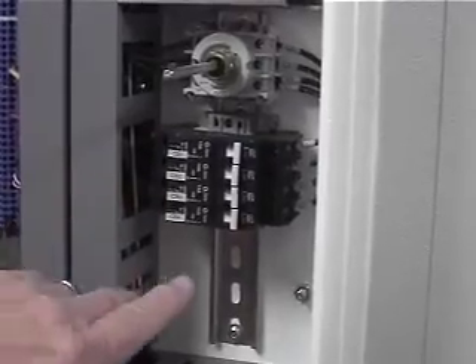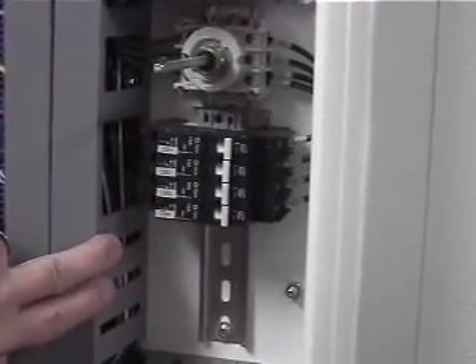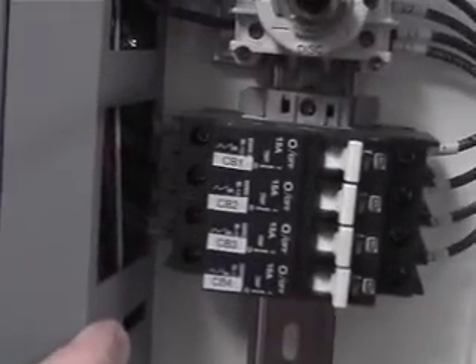One of them's for the fans, one of them's for the lights, one of them's for the receptacles, and this bottom one here, you'll notice the red wire as opposed to the black. That's our 101. 101 is control high voltage. Anything that's in red, installed by the factory, originates from that 101. That's just kind of important to understand.